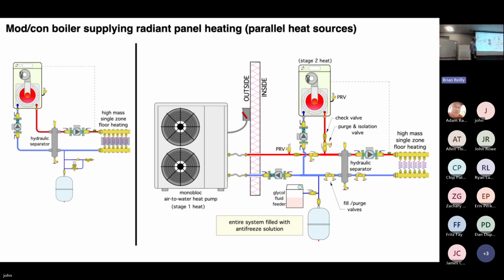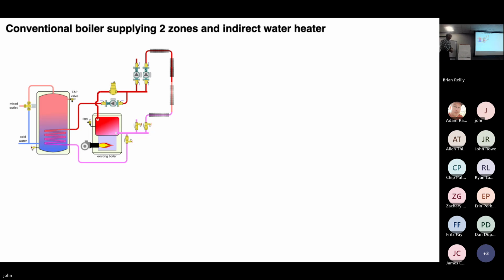So again, it's not complicated. You put the two heat sources in parallel. Each has its own circulator. There's a pressure relief valve, expansion tank. Pretty straightforward. Okay, now we'll get a little more messy here. Here's another residential system, 2 zones of baseboard and an indirect water heater and an oil-fired conventional boiler.